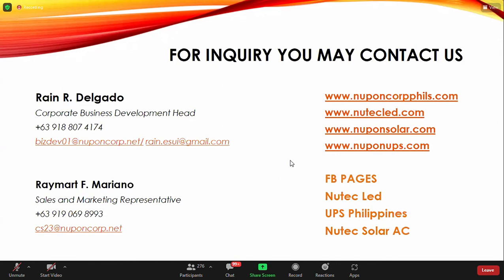Any more questions? I can see someone asking if it does not have the battery, is it applicable to use a battery, Sir Stewart? We normally don't recommend a battery because in solar aircon, this was always my challenge with my partners in China. They always wanted me to have a battery. And realistically, if you use a battery with a solar aircon during the day, it is stealing power which is required to run the unit. So thus you need more panels. So the cost is exponential. So that's why in this initial unit, I don't want to do batteries.